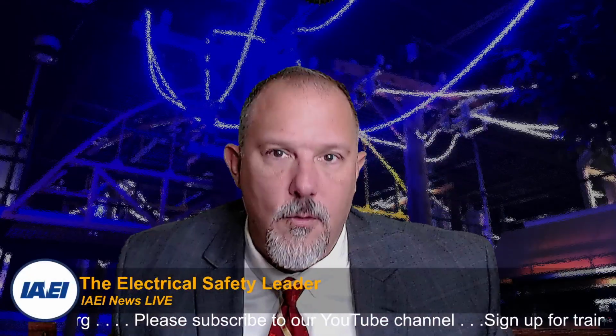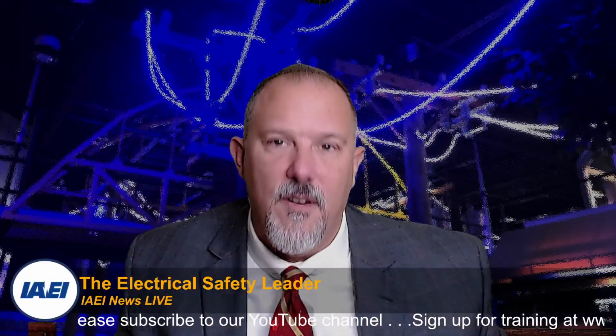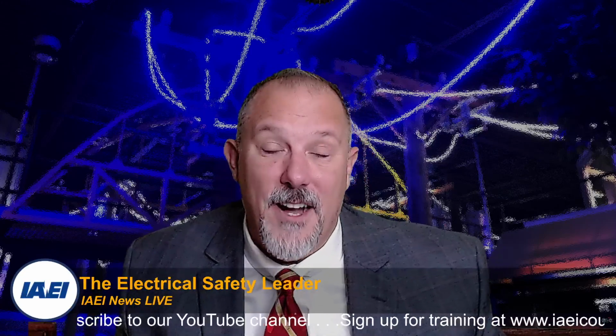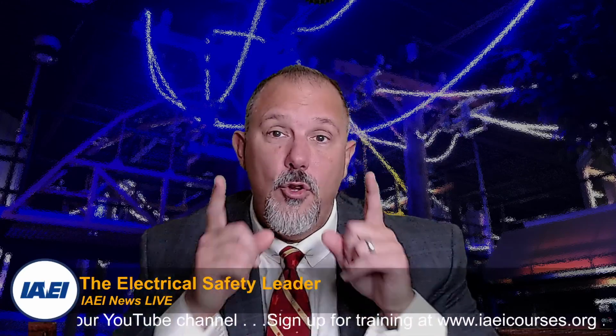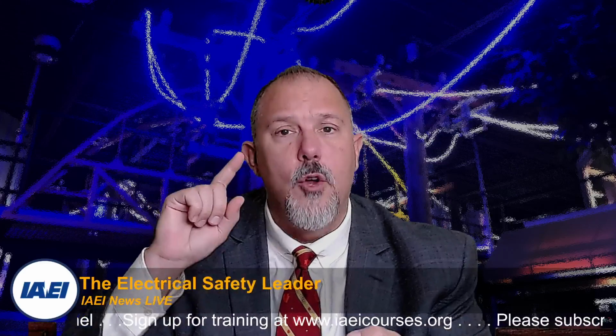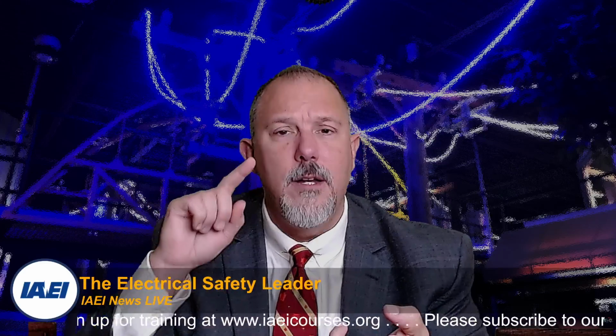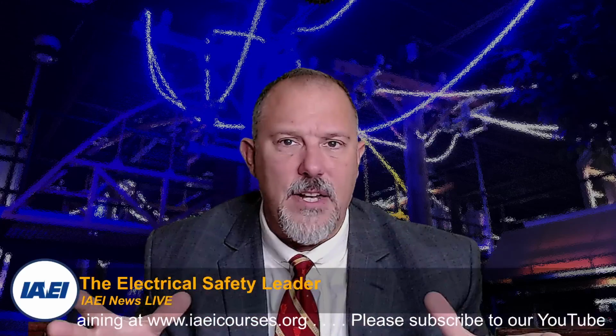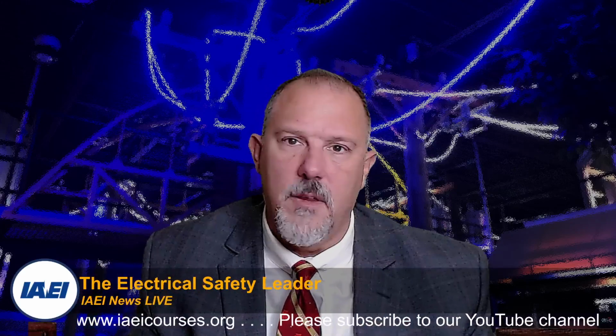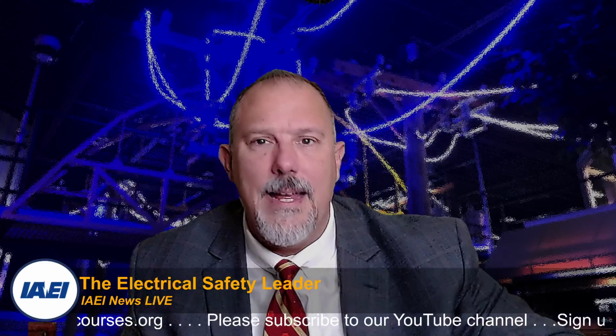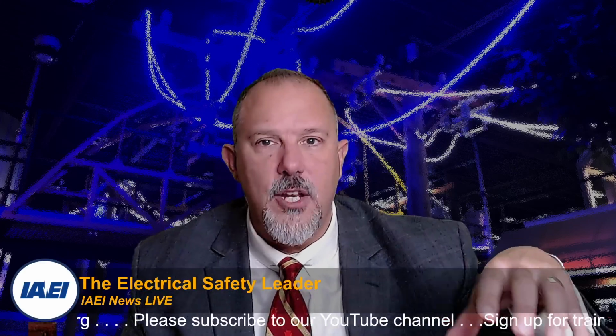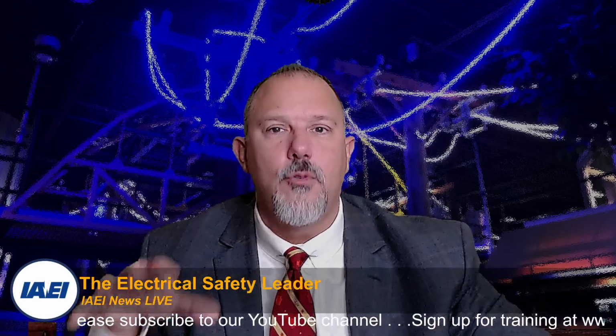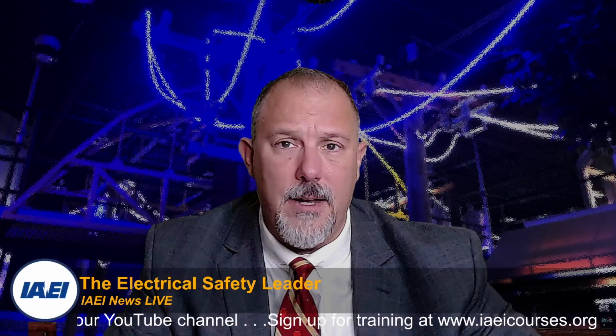That's a 1 hour overview. That's a 1 hour and 12 minute overview of available fault current. You saw the sections in the code that are required for marking the fault current, required for marking SCCR everywhere. Any device you apply in any portion of the power distribution system, because 110.10 tells you you need to make sure that the short circuit current rating is greater than the available fault current at that location. You're not going to get away with not calculating.